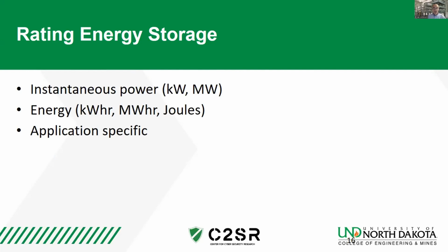You also have energy ratings that go with this. John talked about the battery built at Schweitzer Engineering Labs - the primary purpose was backup power for their manufacturing facility, but they also used it for grid services when it was running. That was a 1 megawatt, 3 megawatt hour system, so it could supply 1 megawatt for 3 hours. That depends on how the storage itself is rated.